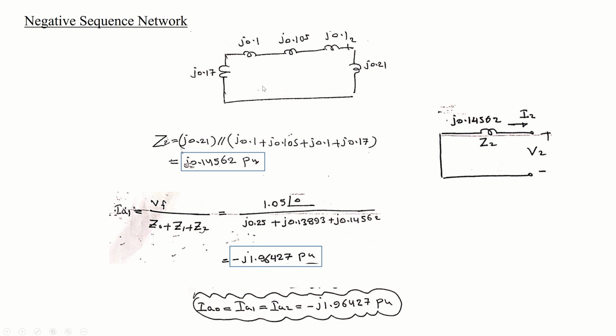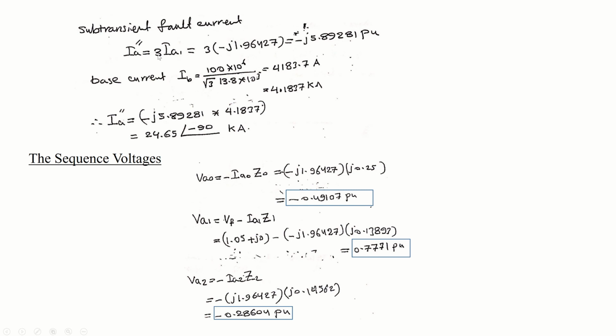For the negative sequence, it is the same but without a source, so you calculate Z2. So all this is added together with this in parallel, and you get Z2, and it doesn't have a source. So this is the value for I2. So Vf divided by Z0 plus Z1 plus Z2, now you have Z0, Z2 and Z1 all together, divided into Vf, and then you will calculate Ia1. Ia1, Ia2 and Ia0 are all the same. To get Ia, just multiply by 3. So you multiply by 3 to get Ia, which is the fault current at phase A, which is the fault that you want. This is per unit.